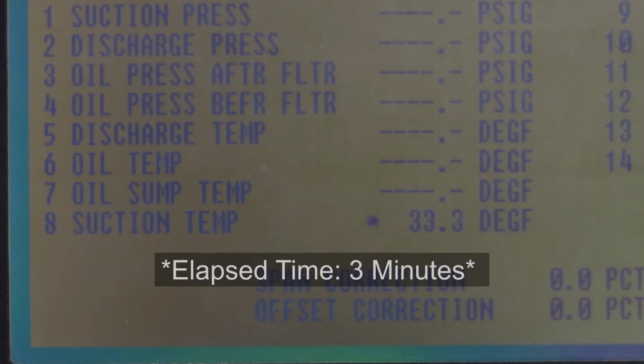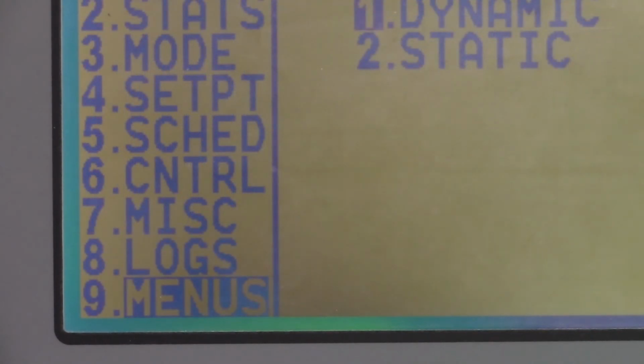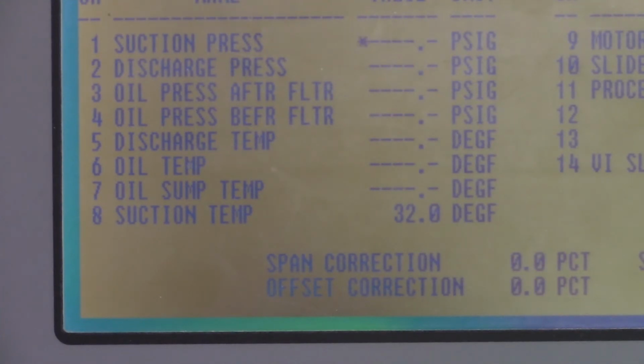Once you have a nice, steady temperature reading, any variation from that 32 degree set point can be reset to exactly 32 degrees. Just enter 32 on the keypad and hit Save. You can go back into the dynamic menu by pressing 1 and make sure that value stays around 32.